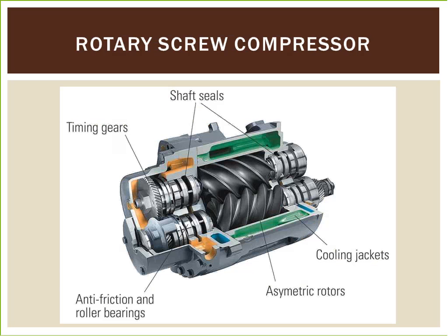Since the cooling takes place right inside the compressor, the working parts never experience extreme operating temperatures. The rotary compressor, therefore, is a continuous duty air-cooled or water-cooled compressor package. Rotary screw air compressors are easy to maintain and operate. Capacity control for these compressors is accomplished by variable speed and variable compressor displacement.